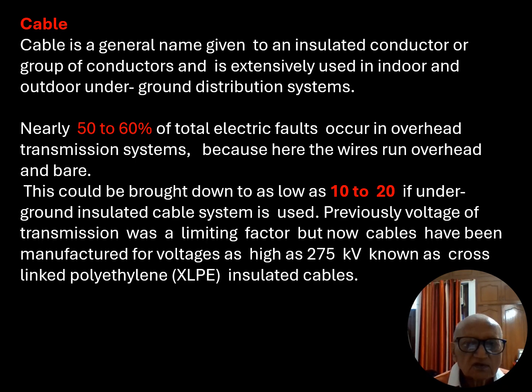Cable is a general name given to an insulated conductor or group of conductors and is extensively used in indoor and outdoor underground distribution systems. Nearly 50 to 60% of total electrical faults occur in overhead transmission lines because here the wire runs overhead and bare. This could be brought down to as low as 10 to 20% if an underground insulated cable system is resorted to. Previously, voltage of transmission was a limiting factor, but now cables have been manufactured for voltages as high as 275 kV in insulation grade known as cross-linked polyethylene, XLP insulated cables.